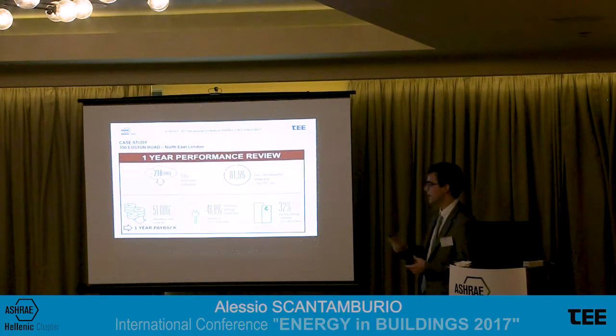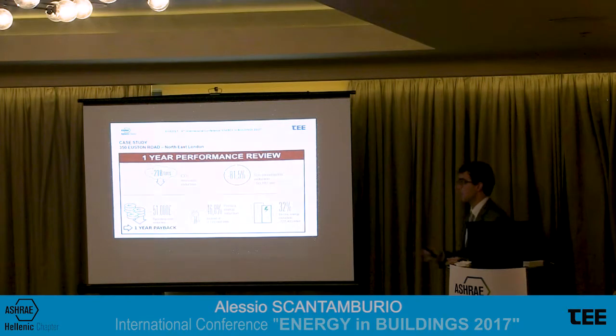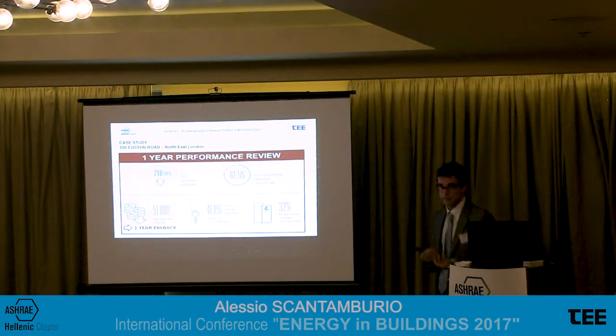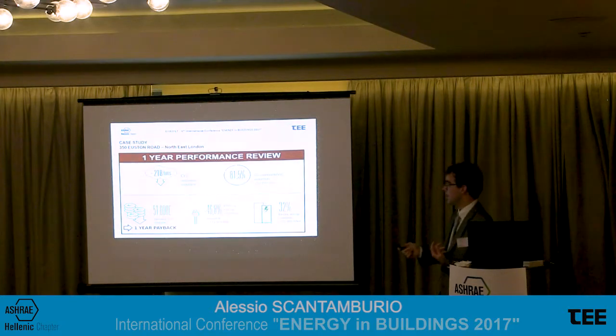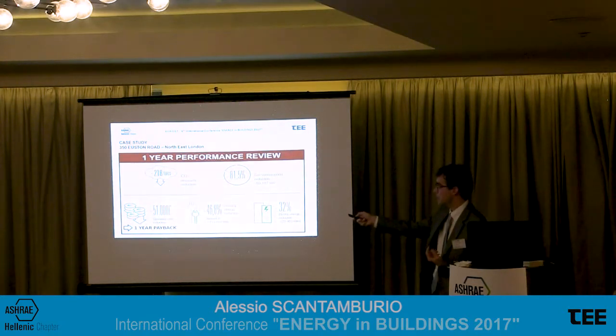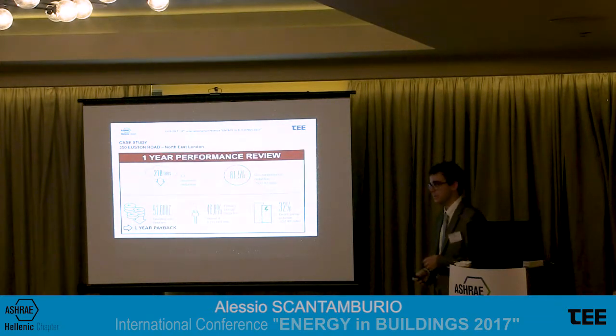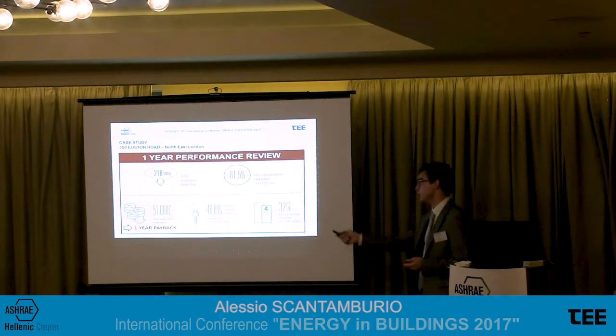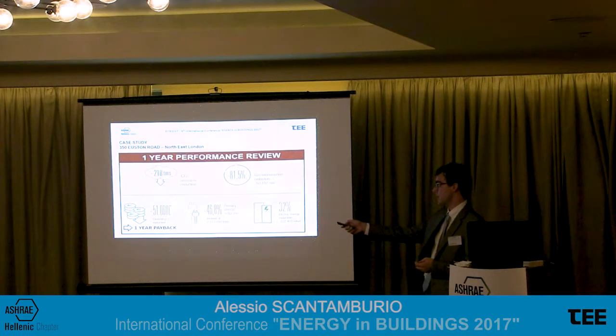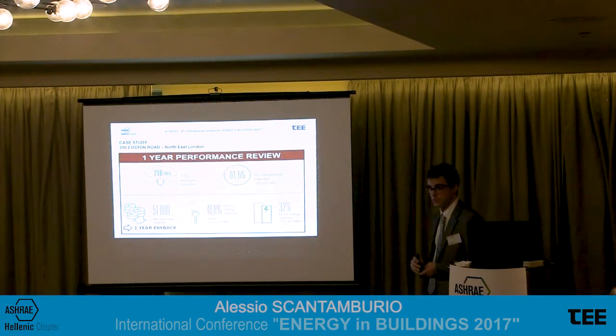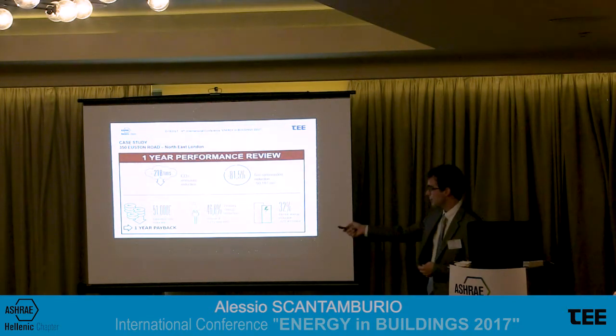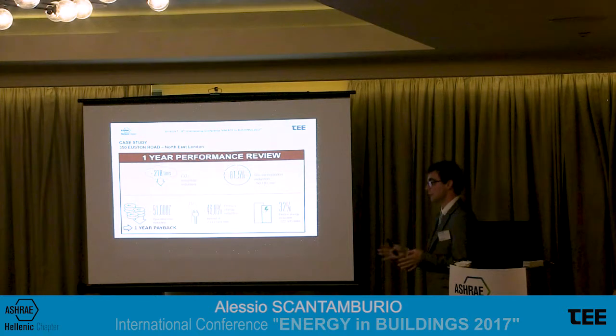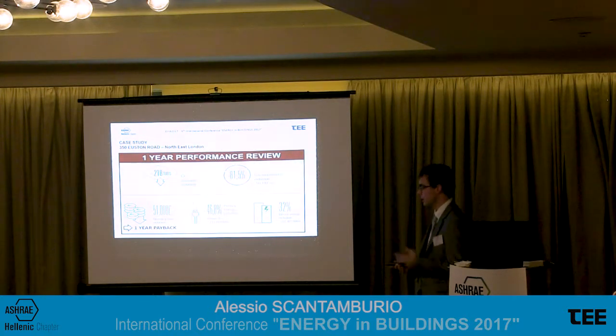Really good, but these are the really interesting numbers. And these numbers are being calculated not by ourselves, but by the tenants of the building. We have a very huge gas consumption reduction, over 80%. This means that the gas boilers were never used in 1 year. And so this means that we have a very huge carbon dioxide emission reduction, over 2,000 tons each year. And most important, we cut the primary energy consumption by nearly a half compared to the previous system, a traditional system, which had a high efficiency chiller.